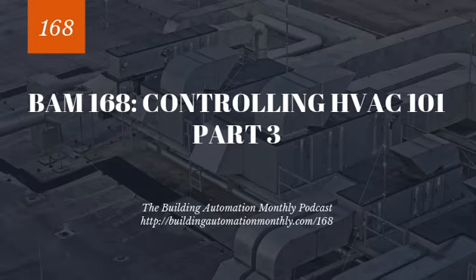All right, so 12,000 BTUs is going to equal a ton. Now, if you've been working with air handlers, this should be fairly familiar to you. You've heard of the rule of thumb, 350 square feet per ton of cooling, and looking at 12,000 BTUs, you can look at your coils, calculate their transfer rates, and figure out what you need as far as tonnage.